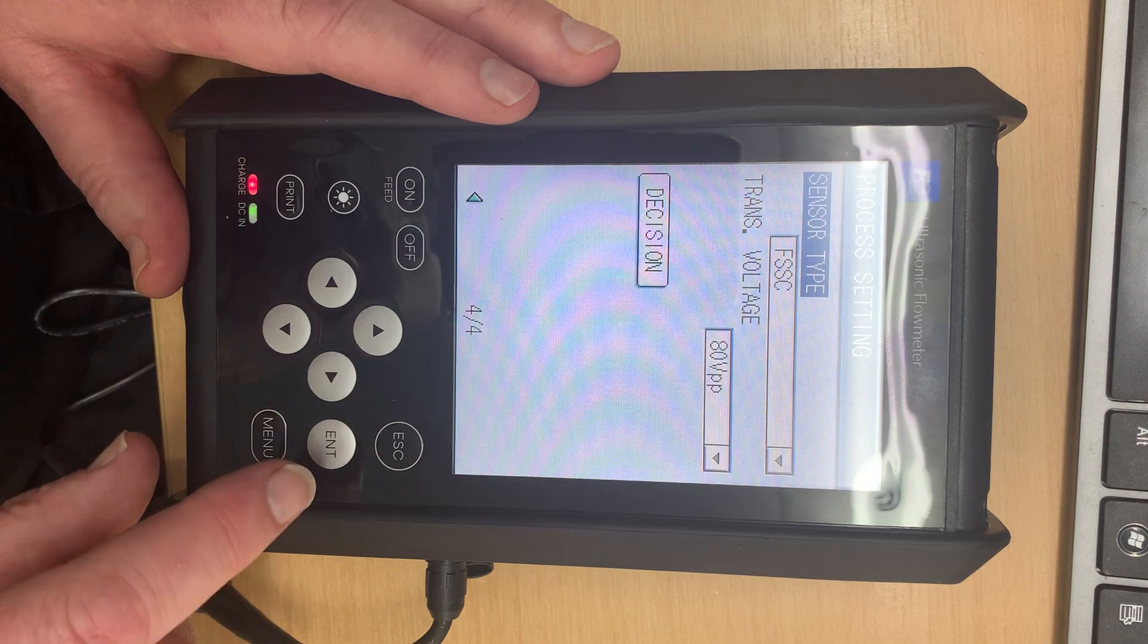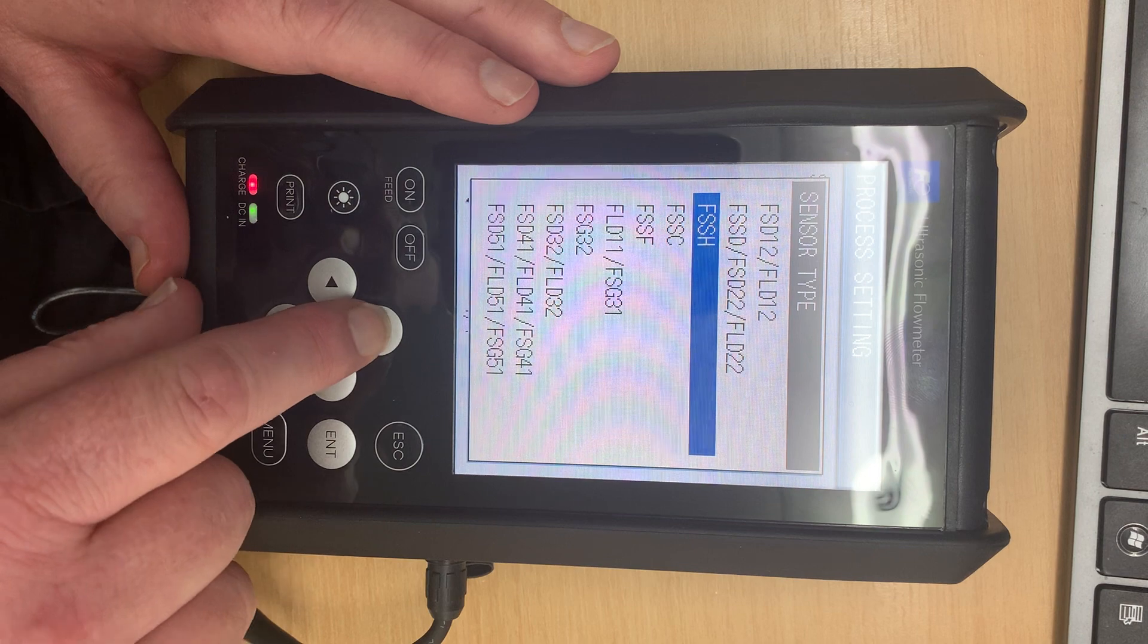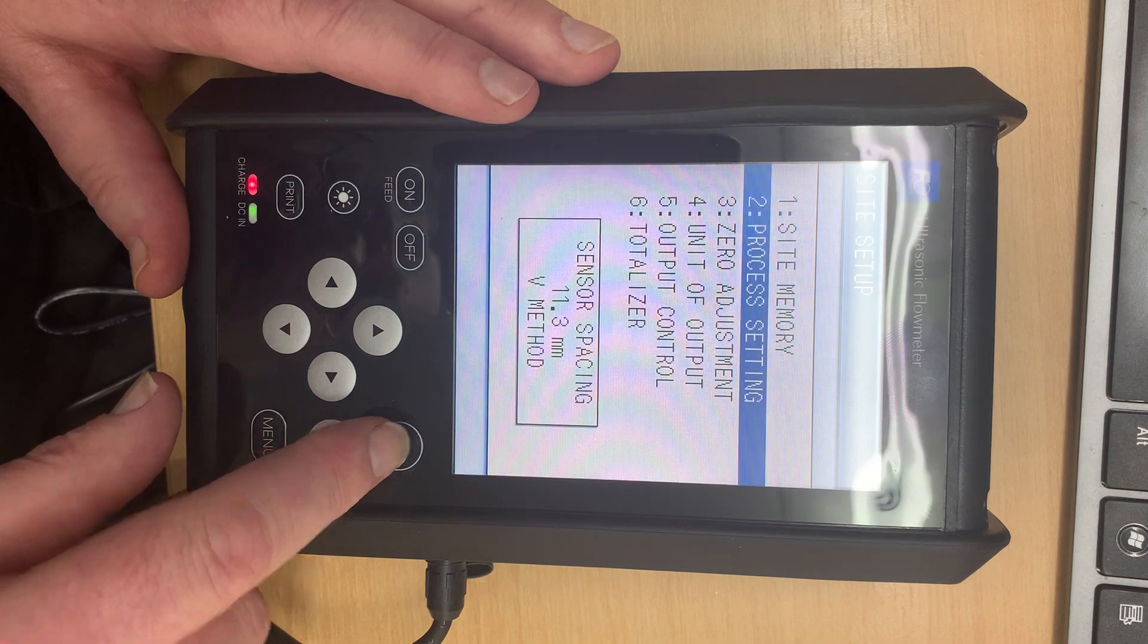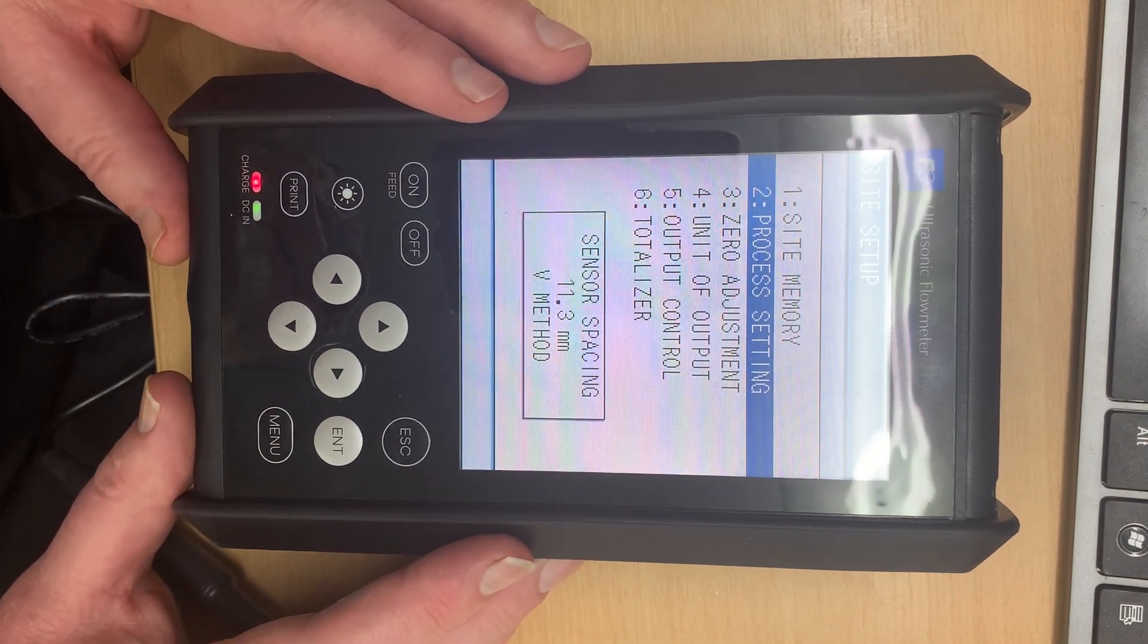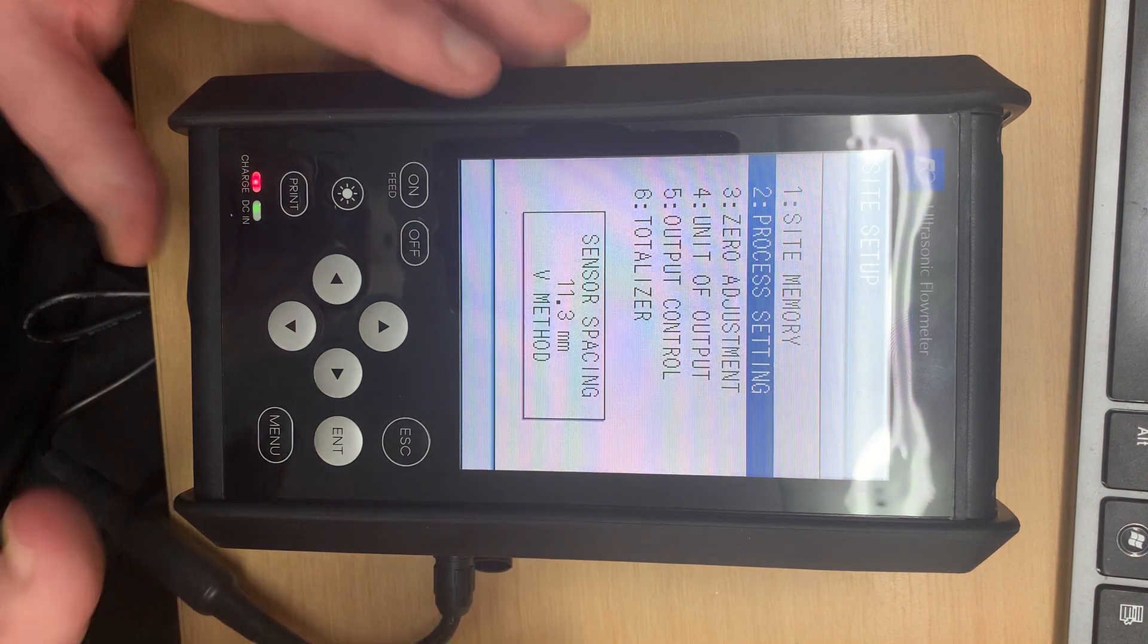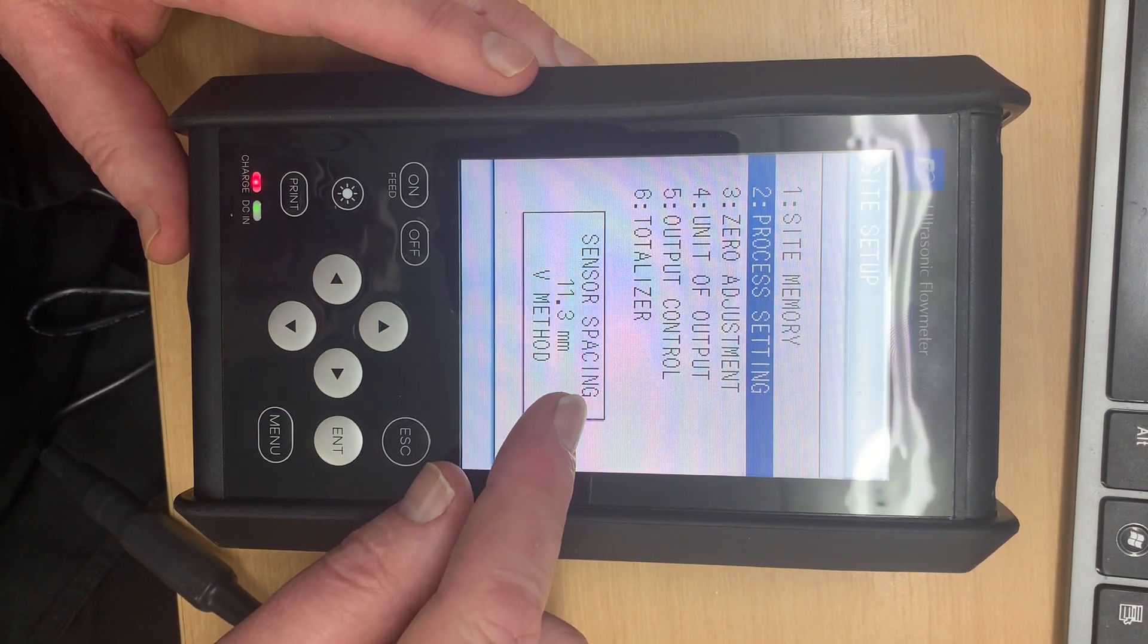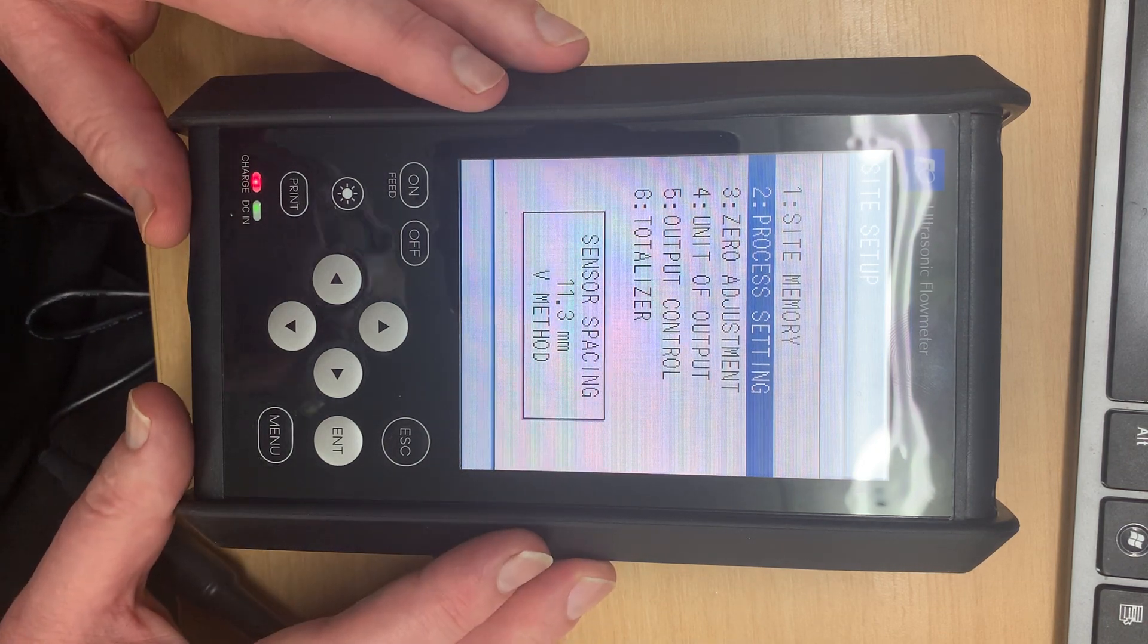Oh, I've probably selected the wrong bar type. So let's go for the smaller one because of the size I've selected. And we'll escape. Right. There we go. So that was the problem. It was defaulting to the pipe size that was too small for that particular setup. So it's saying that in this particular case, we would set 11.3 millimeters as the spacing on the bar.